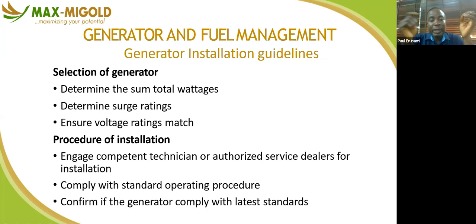Ensure the voltage rating matches. Like I told you, whatever you want to power, if the voltage is out of range, it will not work. If your equipment is rated between 200 and 240 volts, and you go and buy a 260 volt generator, your equipment will not work, only wasted money. If it's below the range, it will not work. It has to match the voltage that is required to drive your load.